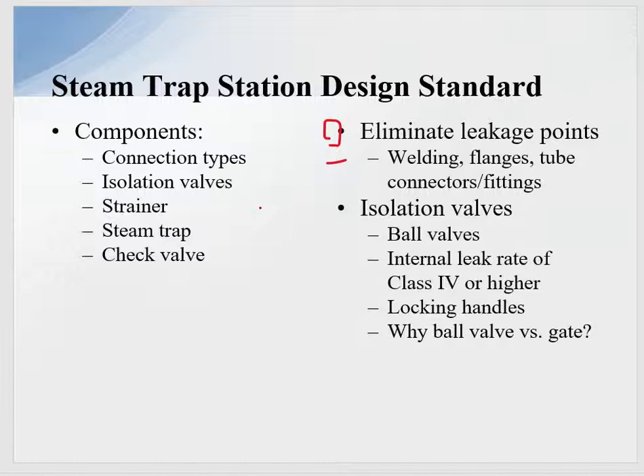Isolation valves — my preference is always ball valves. People ask me: ball versus gate? When's the last time we had any great revolution in a gate valve? 1941. Ball valve technology has accelerated in the last 15 to 20 years, same as butterfly valves. I want a valve that doesn't leak internally. Ball valves will get to Class 4 or higher, so it gives me a positive shutoff. I don't have to worry about steam or hot condensate spitting out on people. It also comes with locking handles. Isolation valves — ball valves, of course. Standard — usually Class 4 or higher.